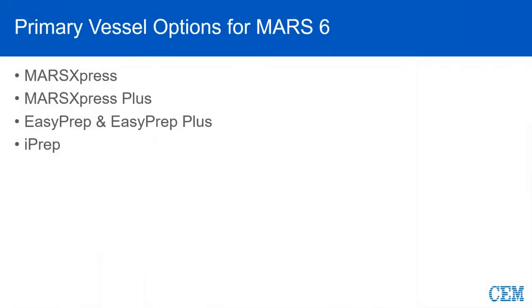With the Mars 6, there are a few different types of vessels that we will discuss today, beginning with the Mars Express. Please note that the Mars Express does come in 10, 20, 55, and 75 mL sizes, all based on your particular application, sample size, and volumes.